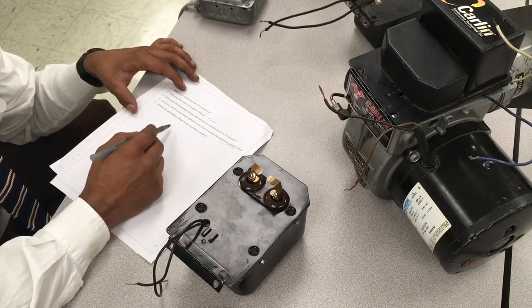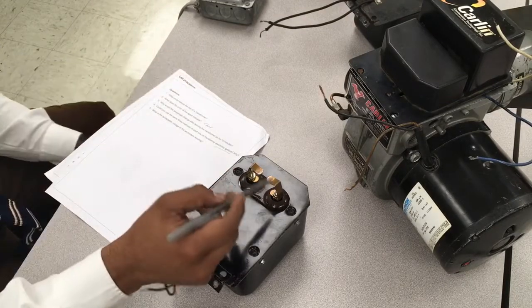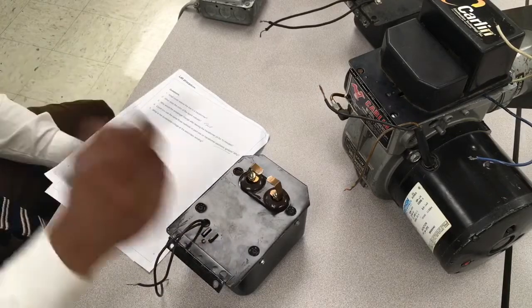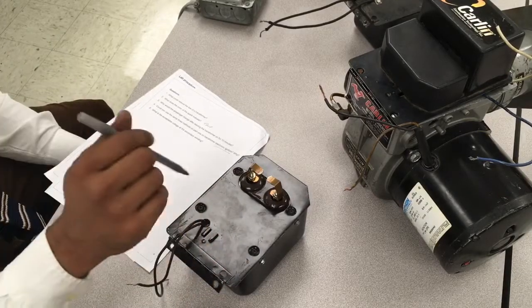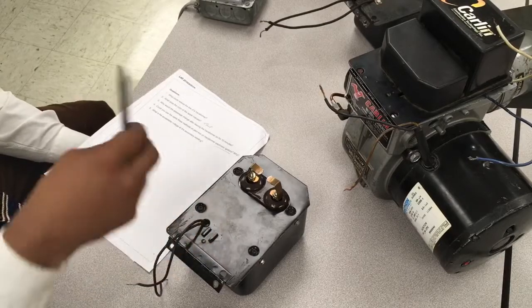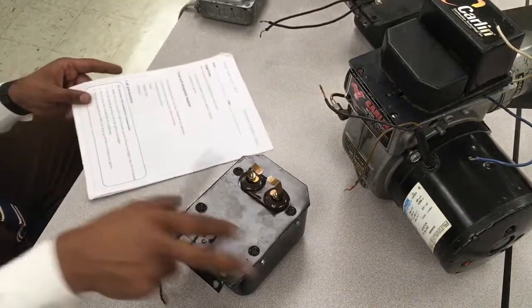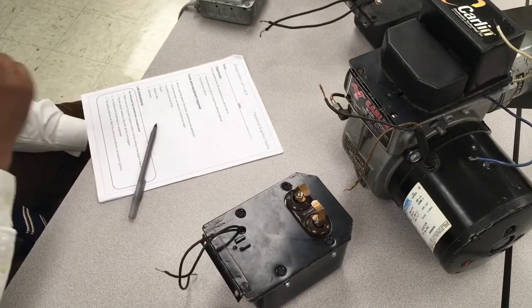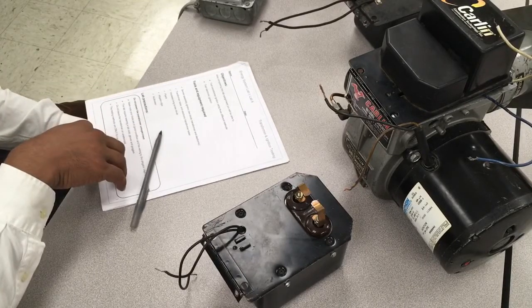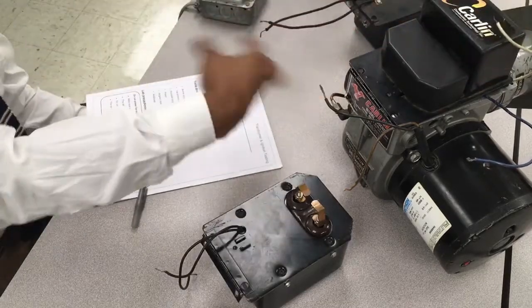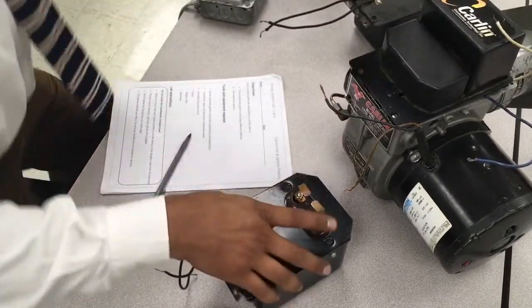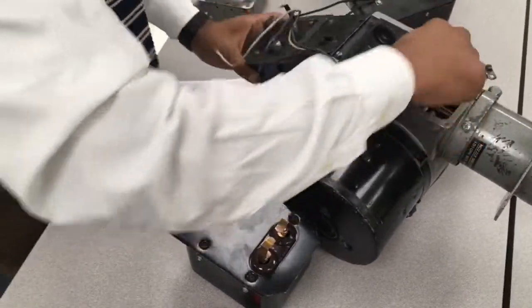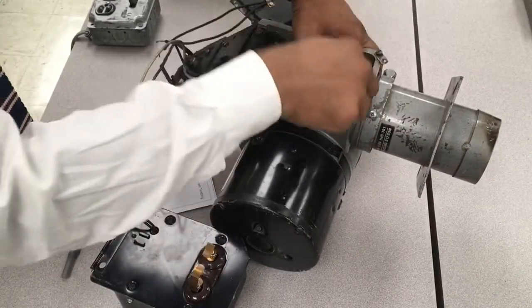What is acceptable voltage for the secondary winding? For the secondary, in order for the spark to jump through air, it has to be at least 10,000 volts. Anything 10,000 and higher is recommended. And again, it's one of the most frustrating aspects of having delayed ignition. Sometimes the spark jumps into the casing. The casing is metallic, so make sure that those prongs sit in the correct location here on these electrodes. And we'll do a whole lab about setting electrodes. See those bars over there? You want those prongs to sit neatly snug on these leads. All right, thank you.